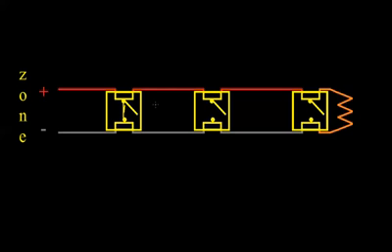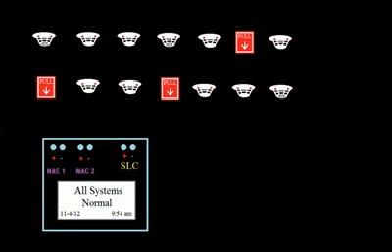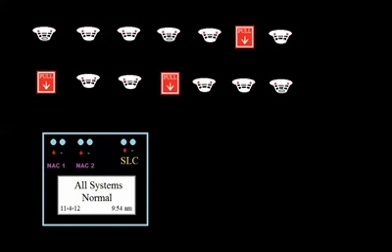Well, that's not at all how addressable panels work, or intelligent panels. You'll hear there is some difference in the terminology between addressable and intelligent, but from my experience, the two terms are used pretty much interchangeably, so we're not going to spend a lot of time on that. That's current monitoring, right? And an addressable panel or an intelligent panel uses something completely different. It uses data communication to communicate with all of its initiating devices.